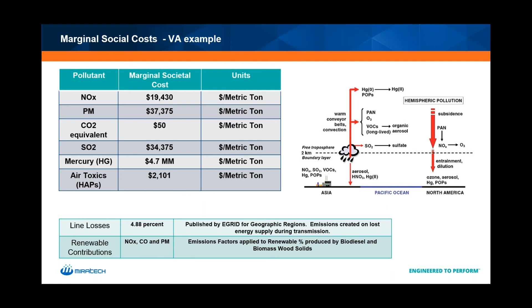In the end, what do we get? We get a generator versus utility ratio, the ratio of the environmental impact. That's all the pollution from our Tier 4 generator times the damaging effects, those social cost numbers I talked about. You get a total dollar amount and compare it to the same number of electrons created by the utility. I used 10 megawatts just because it helps with the decimals, but it's just a ratio, so it doesn't matter as long as you're consistent. Again, it's very close to the power usage effectiveness parameter in theory.